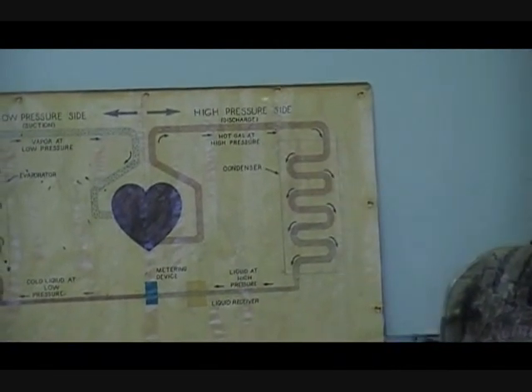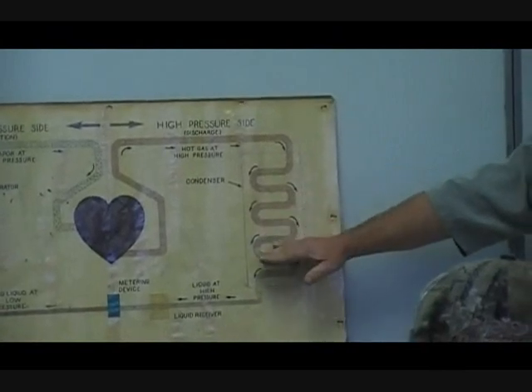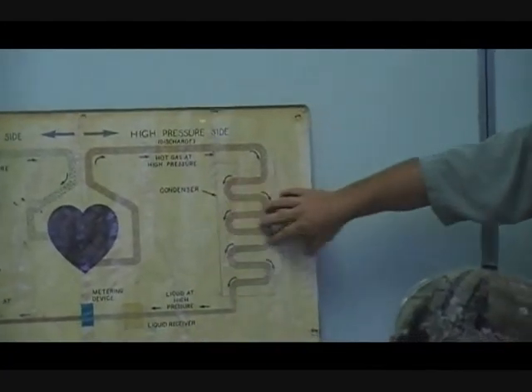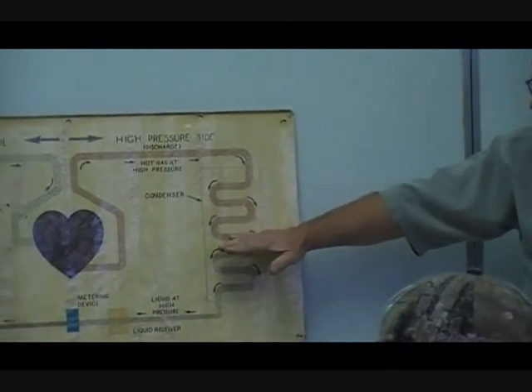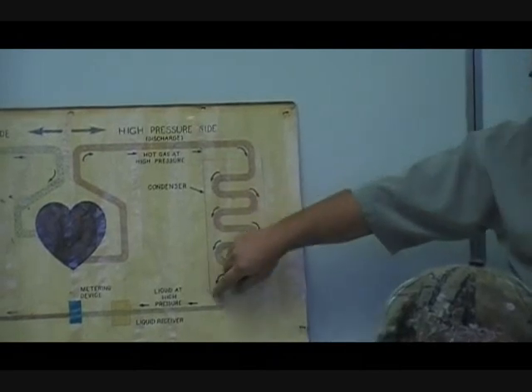The condenser de-superheats the gas. Once that sensible heat is removed, it then goes through a latent heat process. Latent heat changes state — it starts condensing. That's where the condenser gets its name: as the heat is removed from the refrigerant, it starts condensing and turns into a liquid. When it's all liquid, it sub-cools the liquid in the last pass or two. Sub-cooling is sensible heat below the saturation or boiling point. It then enters into the liquid line.